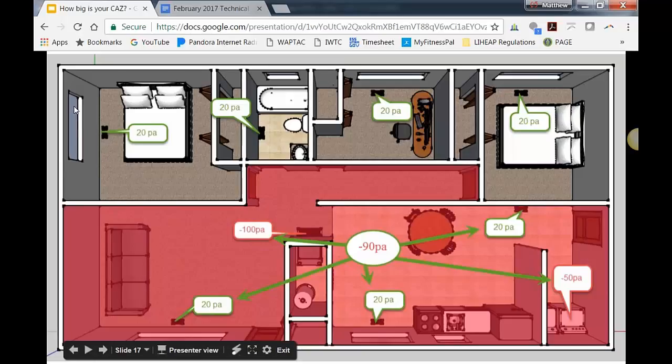With an air conditioner, all of the supply air going into that room now goes directly to the outdoors, and you now have a giant exhaust fan in there. A great example of that is maybe a window-mounted swamp cooler in that bedroom that's not covered with plastic or some kind of cover. Once you close that bedroom door, all of that supply air going in there, however many pascals or CFM, now has a direct path to the outdoors, which is essentially the same exact thing as an exhaust fan. That supply air can't get back to the return, so it's going to go outside, and that will intensify your depressurization.